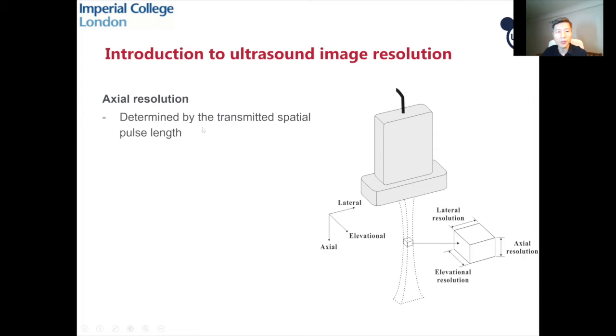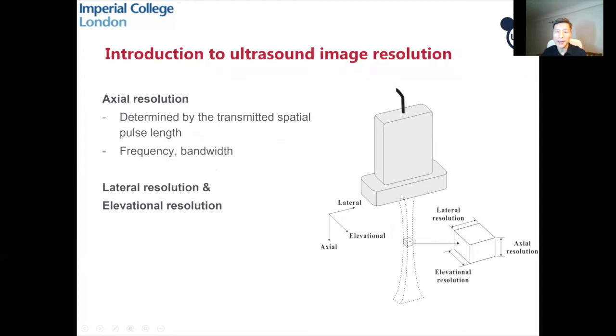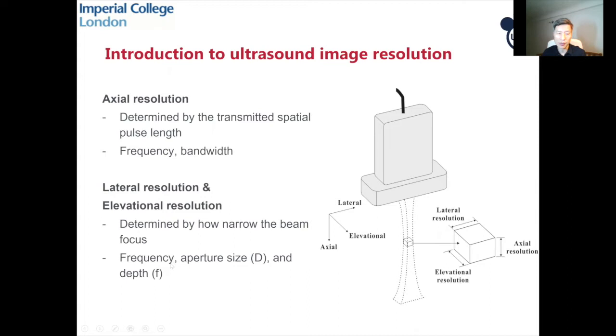Regarding the axial resolution, it is determined by the transmitted spatial pulse length, which is again determined by the transmitted center frequency and also the bandwidth of the system. For the lateral resolution and the elevational resolution, they are determined by how narrow the beam can focus in the lateral and elevational directions, and are again determined by the transmission frequency and the aperture size.